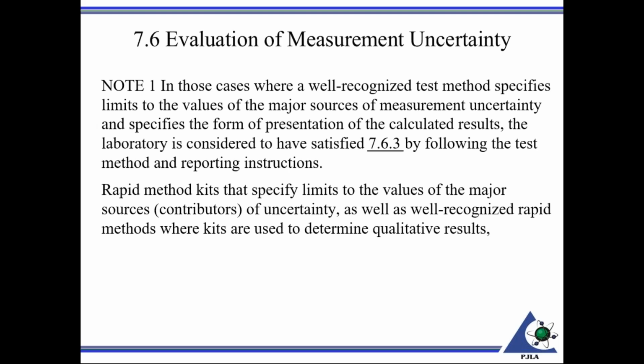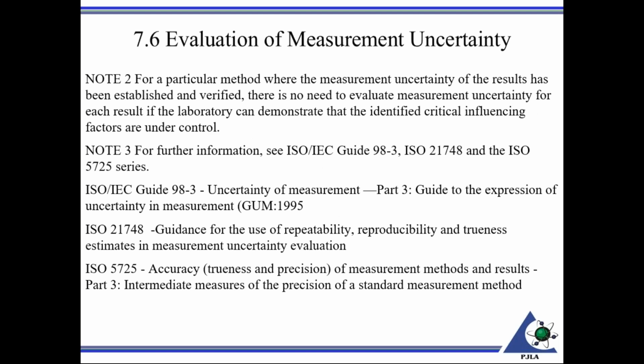So note 1 states, in those cases where a recognized test method specifies limits to the values of the major sources of measurement uncertainty and specifies the form of presentation of the calculated results, the laboratory is considered to have satisfied clause 7.6.3 by following the test method and reporting instructions. For example, rapid method kits that specify limits to the values of major sources of uncertainty, as well as recognized rapid methods where kits are used to determine qualitative results, would fall into here. Continuing, for a particular method where the measurement uncertainty of the results has been established and verified, there is no need to evaluate measurement uncertainty for each result if the lab can demonstrate that the identified critical influence factors are under control.